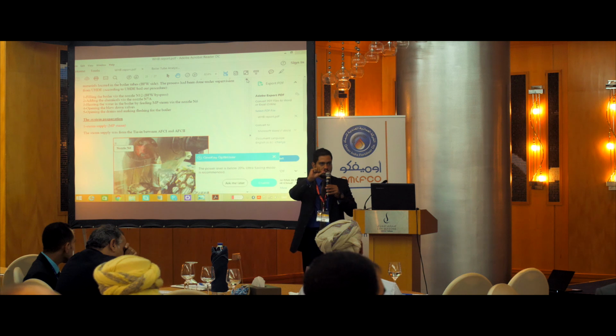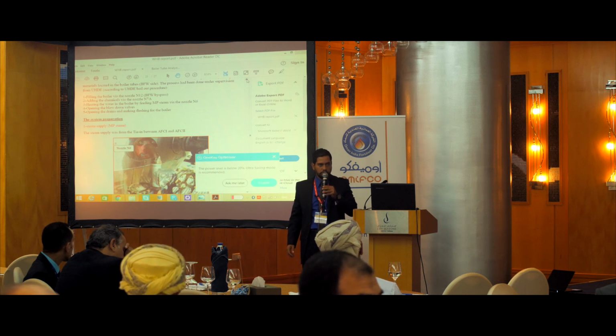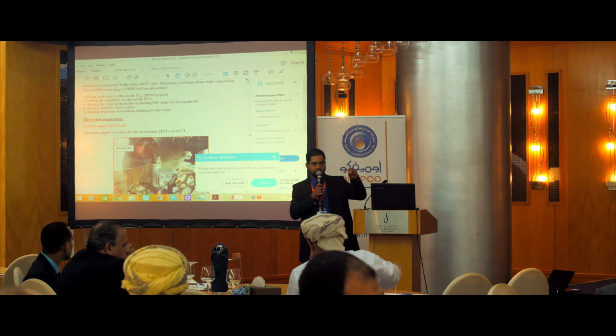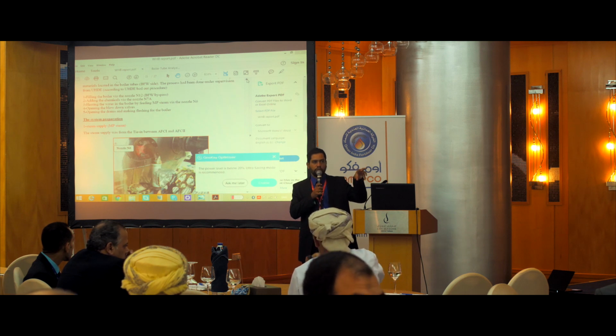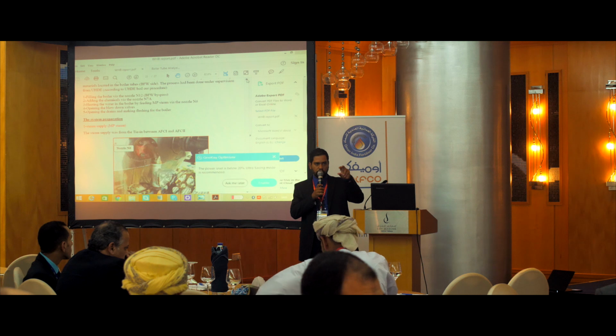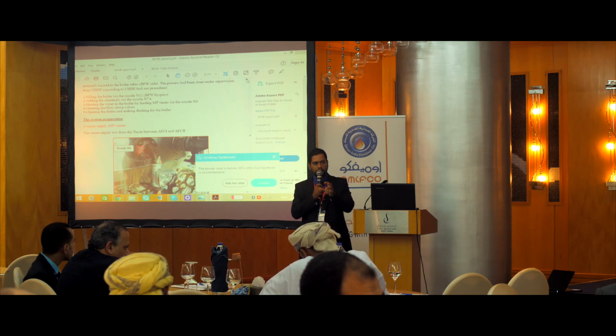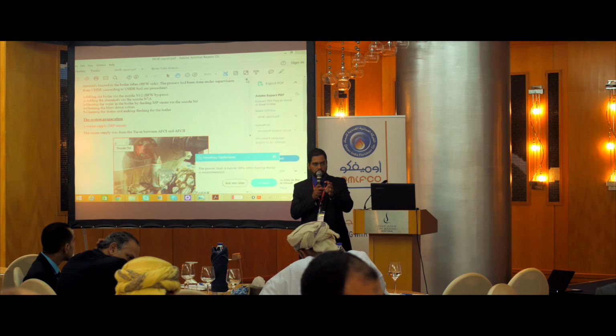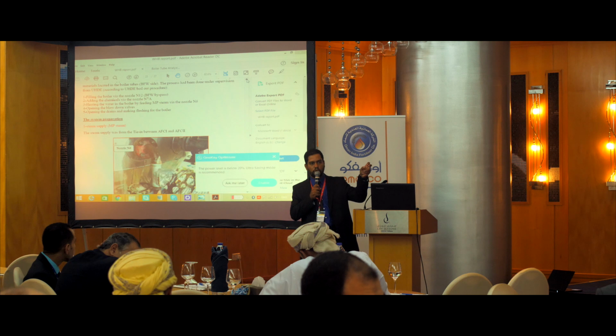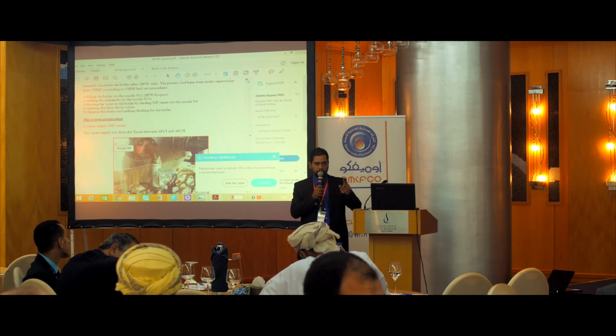The pH, I think, was not well cared for in this condition. The hydrogen attack exists in the main boiler, but the low pH caused damage in the tubes of the waste heat boiler. At what pH? 4.5. Yes.